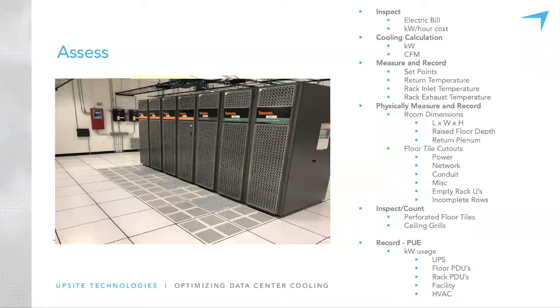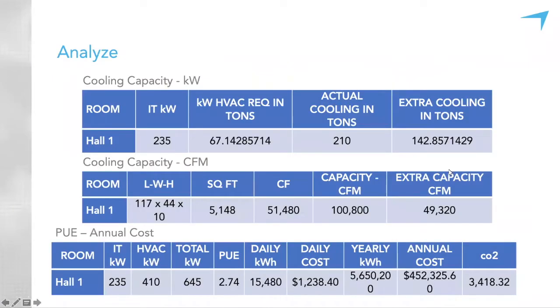We get into a data center, we feel that these racks are a little bit too warm, so we must not be getting enough air, so let's throw another row of floor tiles in. When we do this, we are essentially decreasing the static pressure and decreasing the stratification. We no longer can get the supply air up as high as we need to, and we start this self-perpetuating cycle where everything gets entirely too hot.